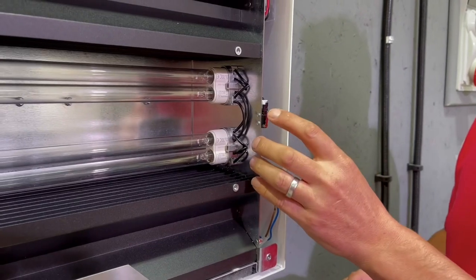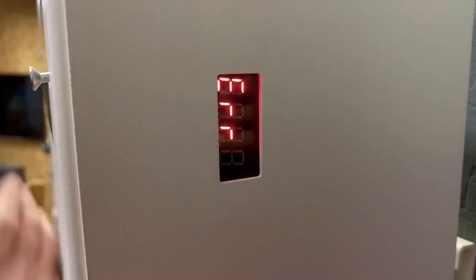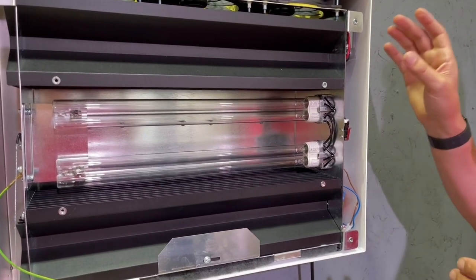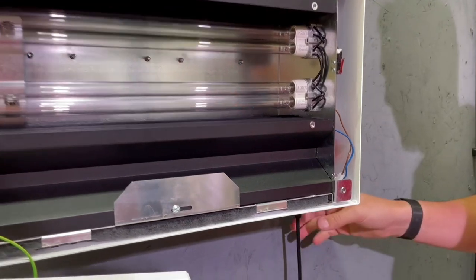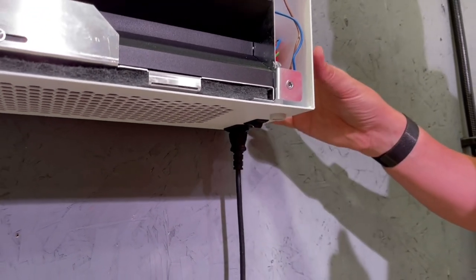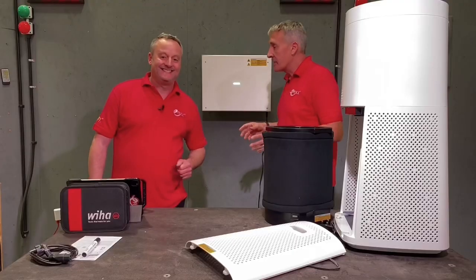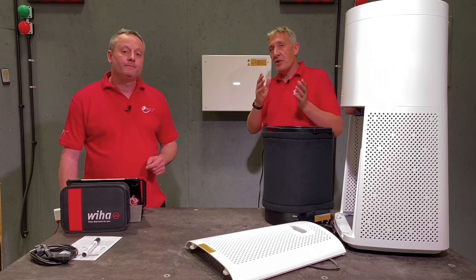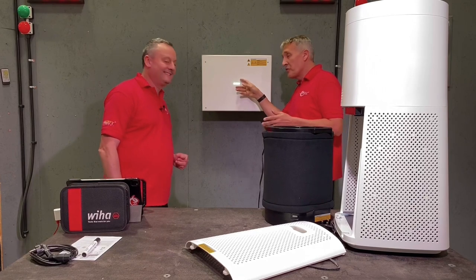We've got this micro switch here that as soon as you start trying to remove the cover will switch the tubes off. If you push it back in, it triggers the control system and presents an error message, so you have to cycle the power again. The display on the side gives you the number of operating hours for the lamp — they need to be changed every 9,000 hours — and then we've got our power inlet, fuse, and a switch. The recommendation is you switch it off before starting any maintenance. Just put the internal cover back on — time to power it up. You can hear the satisfying hum of the fans, giving reassurance that air is actually moving. You can also tell the UV lamps are on through this window at the front, and there is a filter in there so that's not UV light leaking out into the room.